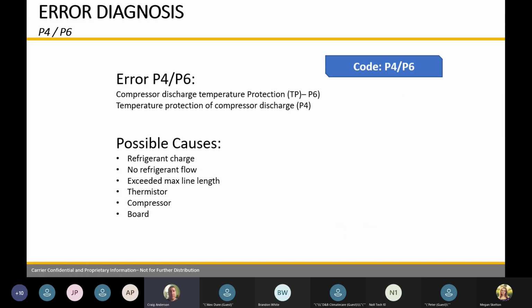So different codes, P4, P6. Every unit's going to be a little bit different with what a P4 and P6 means. We're looking at compressor discharge temperature protection. So we're looking at refrigerant charge, refrigerant flow through the EE valve, exceeded line lengths, compressor, bad board, stuff like that. Gives you an idea where you need to go to look for what the problem is.